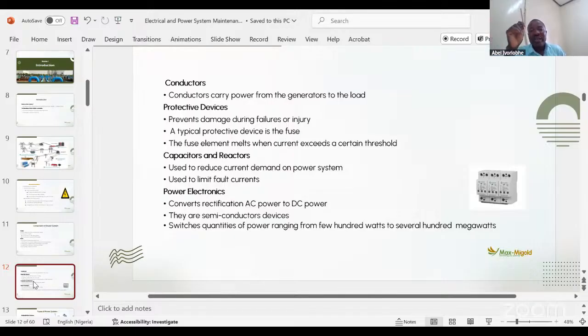If you use a precise size of a precise breaker as rated or as indicated, the breaker will open whether you are there or not. That's why we recommend circuit breakers of rated capacity to be used to distribute your load.